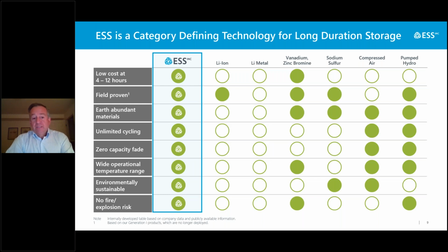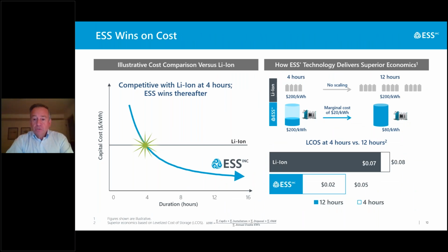So on the cost side, I mentioned that the marginal cost of adding duration with a flow battery is probably one of the key attributes. With a lithium ion, you can obviously go up to 8 or 10 or 12 hours, but what you're doing is you're adding cells. And so it pretty much flatlines the capital cost as you extend the duration out beyond 4 hours. And obviously what we're doing on a flow battery is we're adding electrolyte. When that electrolyte is iron salt water, it's very inexpensive. So you can see that it drives down the dollars per kWh capital cost on here.